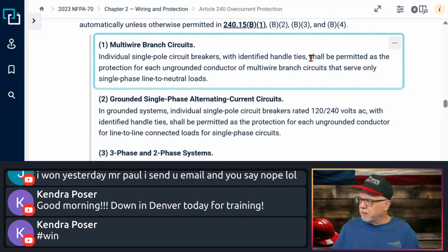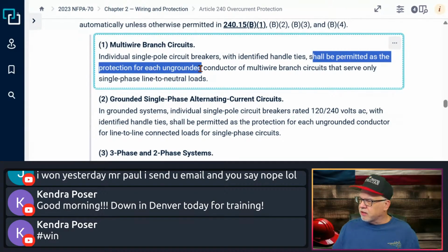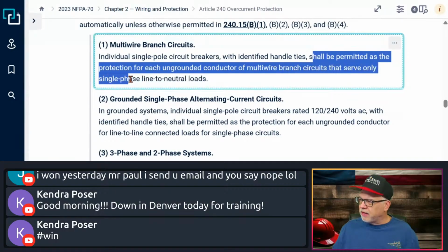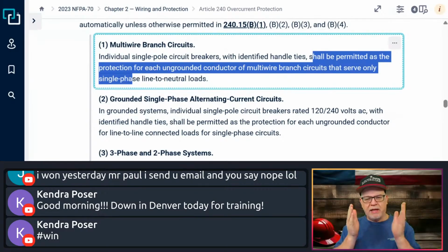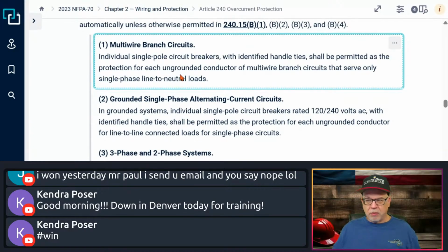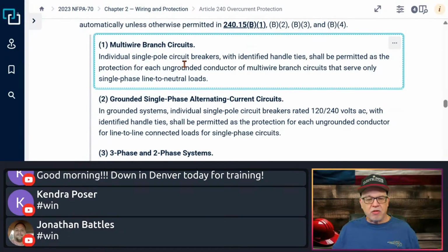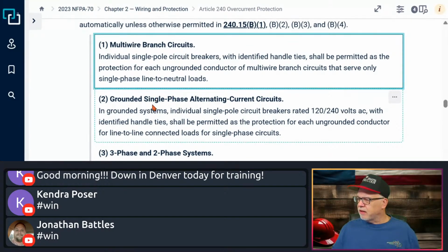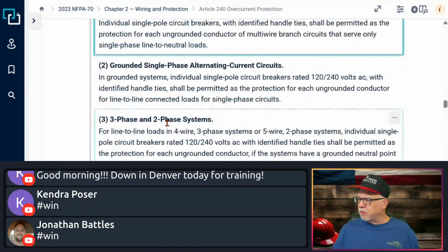It says shall be permitted as a protection for each ungrounded conductor in a multi-wire branch circuit that serves only single phase line to neutral loads. So it's a multi-wire branch circuit, leg A, leg B, they're sharing a neutral. Okay, so those are line to neutral loads. All right, so I'm allowed to do that, and I can use two singles if I want to do that, as long as I have an identified handle tie. Right? And then you have other different allowances down here, but that's the main one.